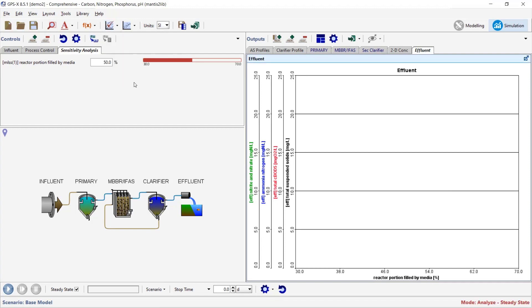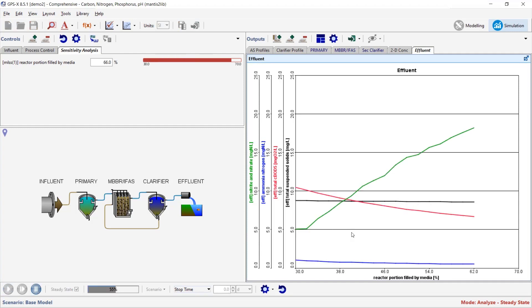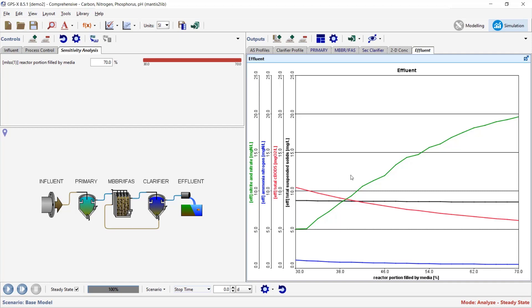Starting with the MBBR format first with RAS set to zero, I'll set it to analyze mode and run it from 30% to 70% fill fractions to see what that does to our effluent. Not surprisingly, both COD and ammonia go down as you add more media. Interestingly, nitrate and nitrite actually goes up as fill fraction increases — we're getting more nitrification. I suspect there was some denitrification occurring in the anoxic portion of the biofilm at lower fill fractions. There's very little change in effluent solids because we don't have conventional activated sludge, so we don't have to worry about overloading the clarifiers with mixed liquor.